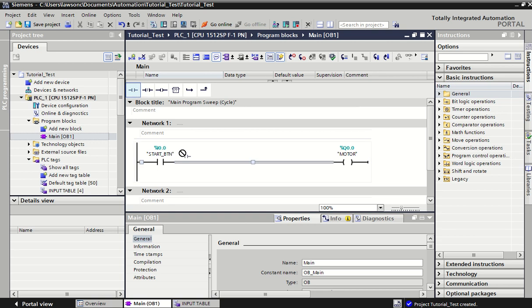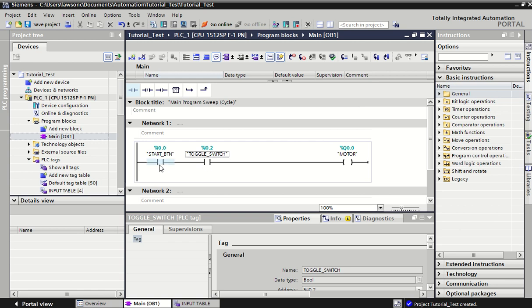Another type of function is what's called an AND scenario. If I put the toggle switch in series here, we now have an AND scenario in the sense that one input AND another input must be pressed in order to get the output. Watch the flow of power — we get up to here and we're waiting for the start button to be pressed, then we're waiting for the toggle switch to be pressed. Once both of them are pressed, we'll get power. If we open or turn off any one of them, that will break the flow of power to the motor and it will turn off.